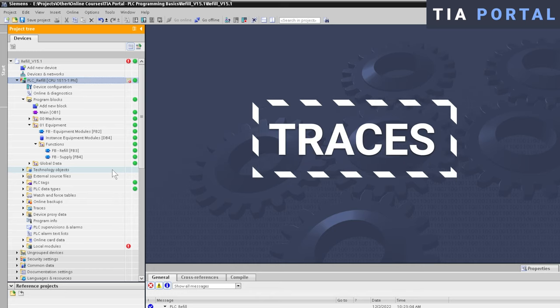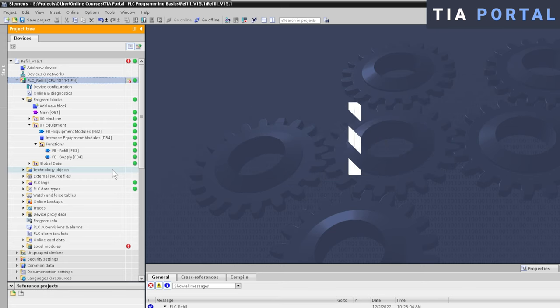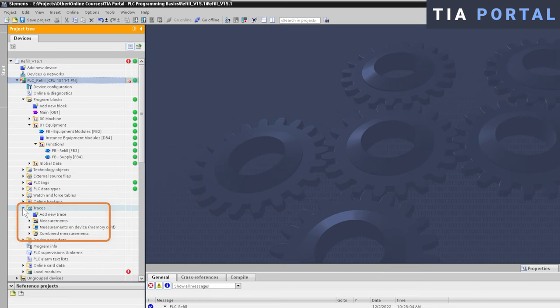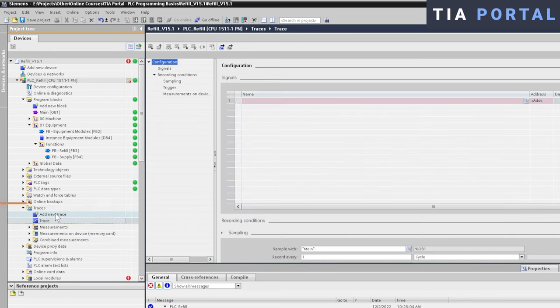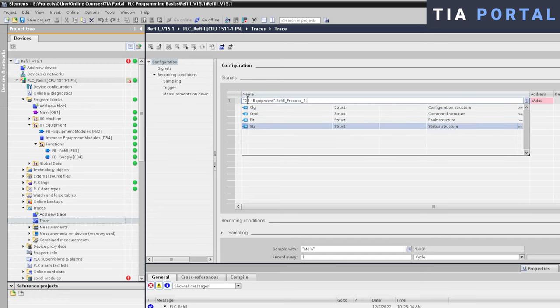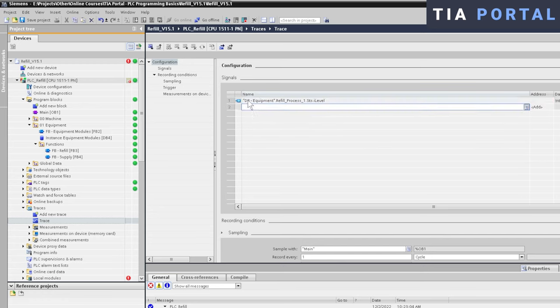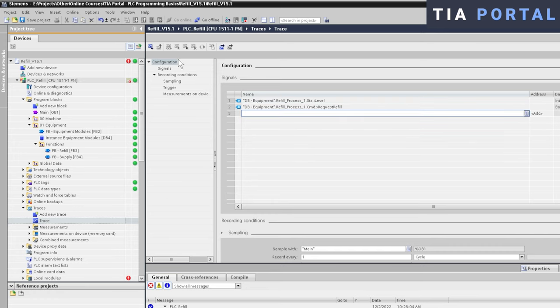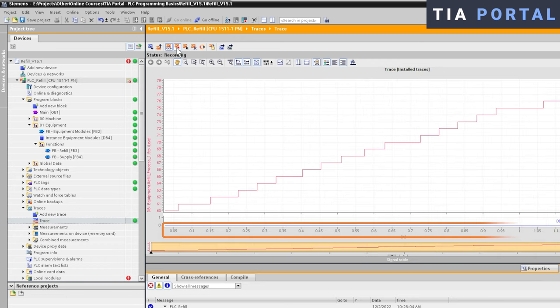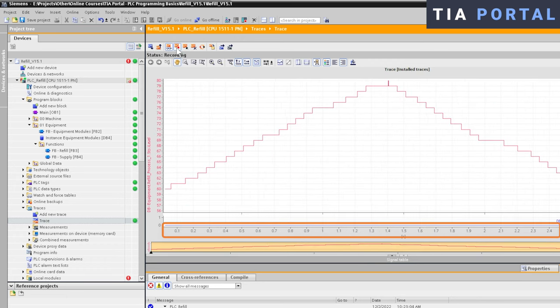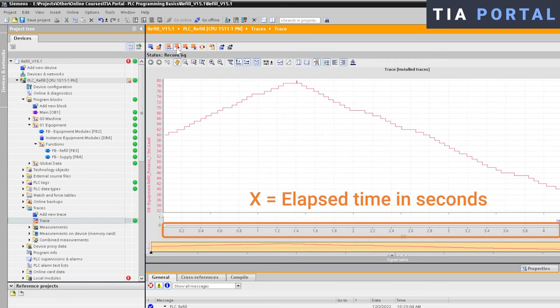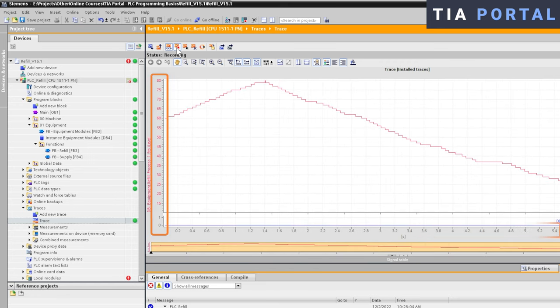In TIA Portal, you can easily create a new trace by going to the Trace folder and adding a new trace. In the configuration window, we can then add the tags that we would like to record, like for example the water level and the refill request of Refill Process 1. Now we download the trace to the controller and we start recording. At the bottom axis, the X axis of the trace, you can see our timeline in seconds. And on the vertical axis, the Y axis of the trace, we have the range of both of our signals.